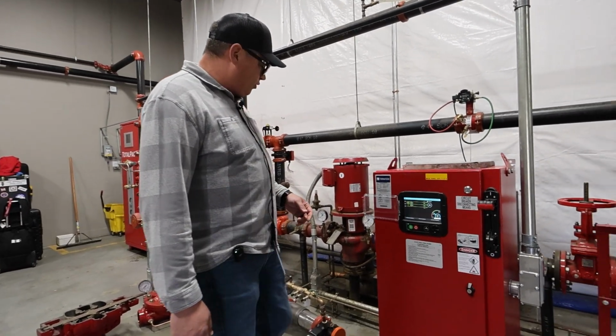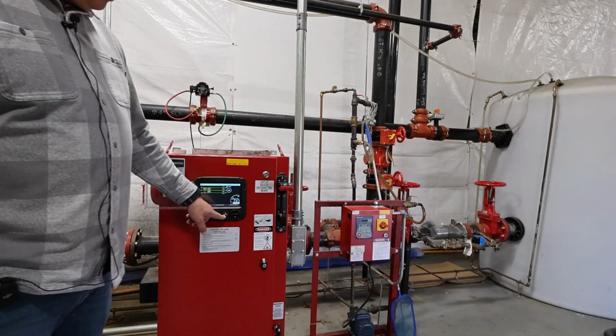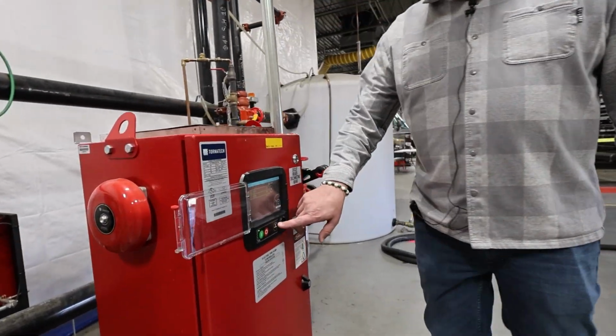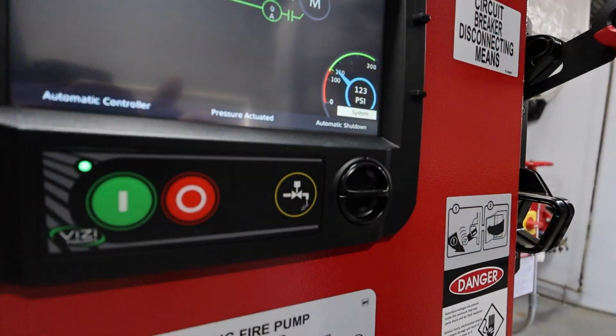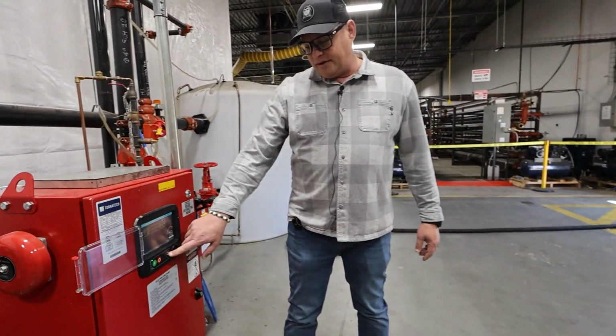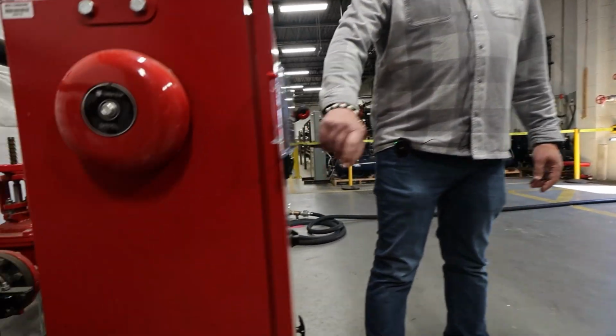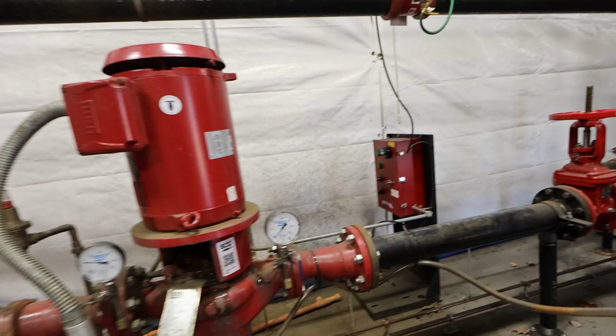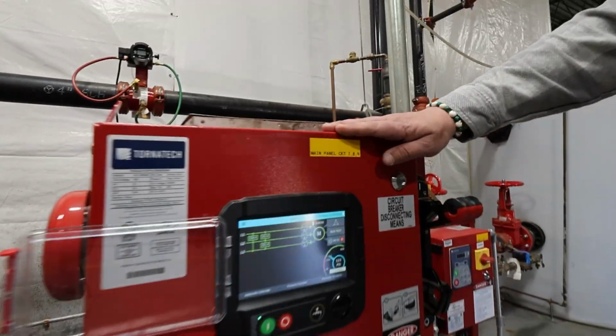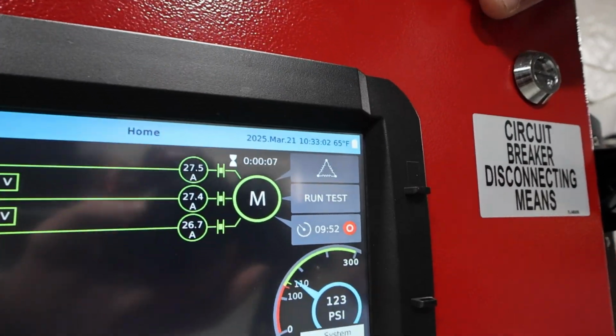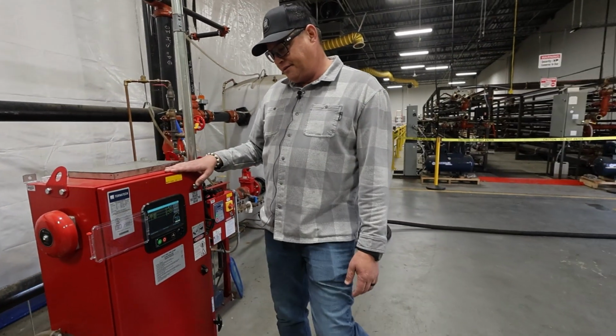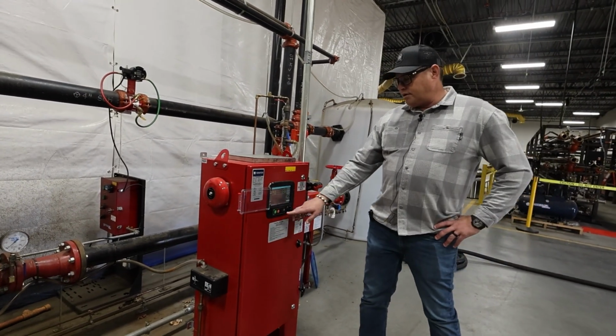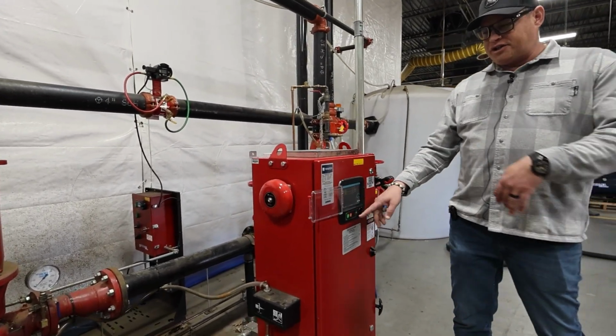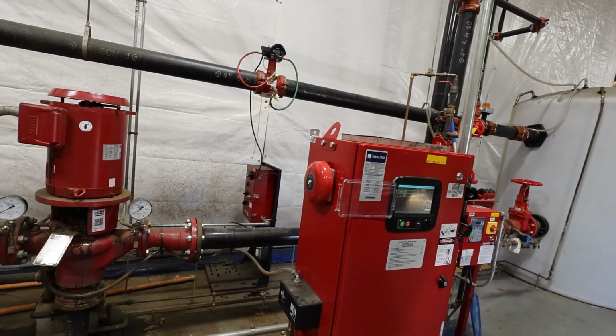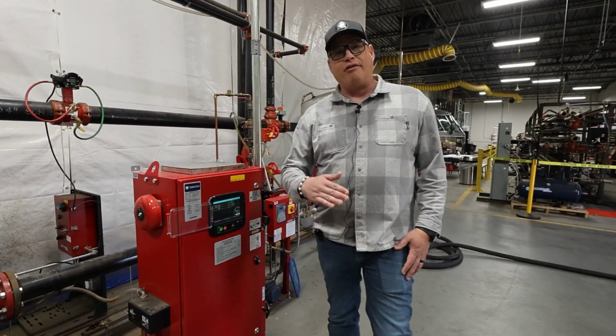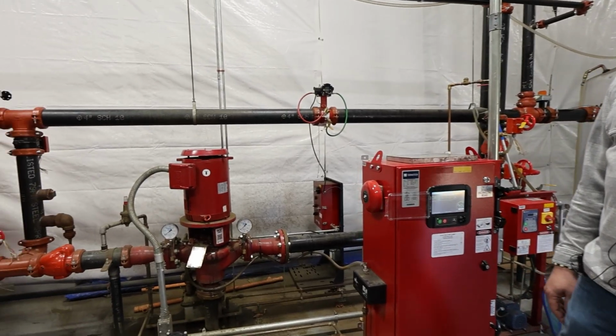We've ensured that fire pump does start in manual. And then the next thing that we'll do is we'll hit our run test button. And this run test button is very clear. It looks like a faucet with a valve on it. The new Tornatechs look slightly different, but let's go ahead and start. So you can see here, last time it said manual, this time it actually says run test, and there's a timer counting down from 10 minutes. Yeah, and that'll automatically shut the pump off after a 10-minute run time. We just simulated our monthly run test, but had we let it continue to run, it would count all the way down to 0 and then shut off. Yep.